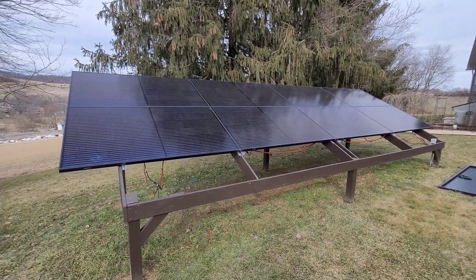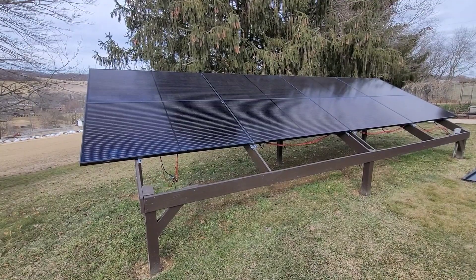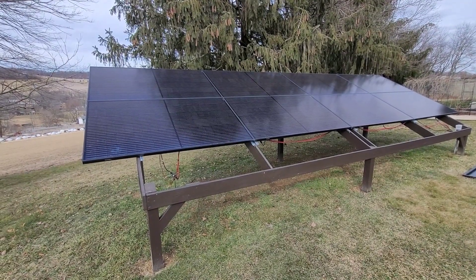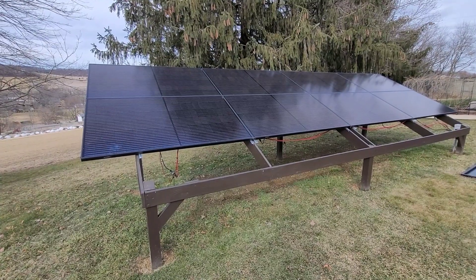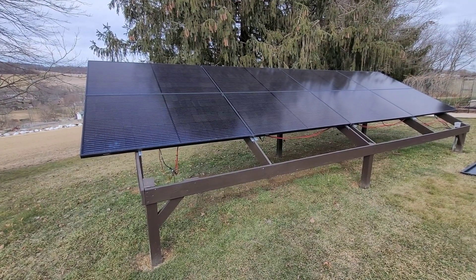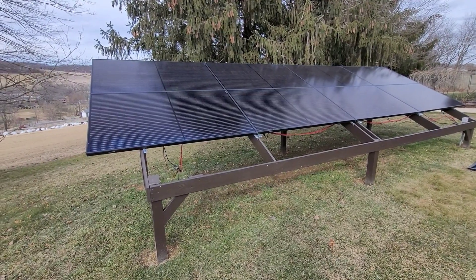So you're going to only see one Midnight Classic 250 inside running on the battery system. And that's before I added the four extra 200 amp hour AGM batteries. You can actually mix the lead acid with the AGMs — they're close enough to mix. I've already verified that with Midnight.